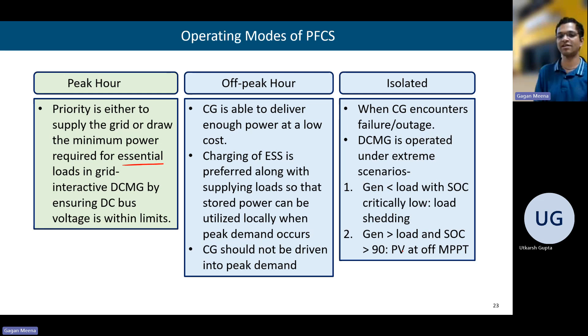The battery can be charged. So charging of battery along with supplying load, so that stored power can be utilized locally when the peak demand occurs. And in this case also the charging should be in such a way that it does not create a new peak demand during the off-peak hour. All this we need to take care of. And in the isolated mode, or when the conventional grid encounters failure or outage, there will be isolation, and the DC microgrid is operated under extreme scenario when generation is less than the load with low SOC. In that case, there will be load shedding. And if generation is more than the load and SOC is more than 90%, which was the case we were discussing, then the PV will operate at off MPPT.